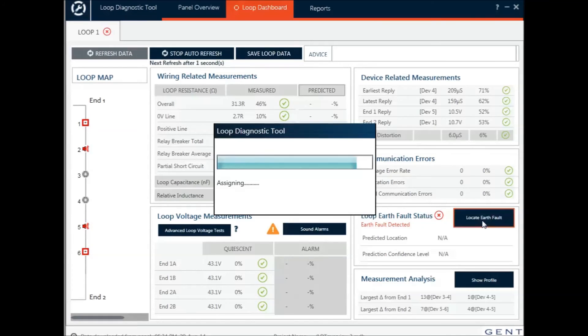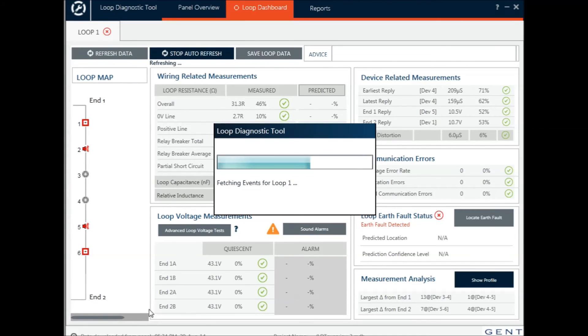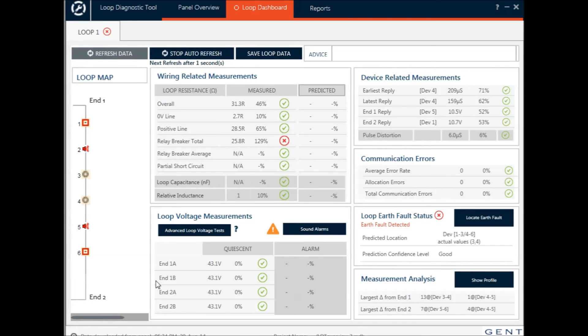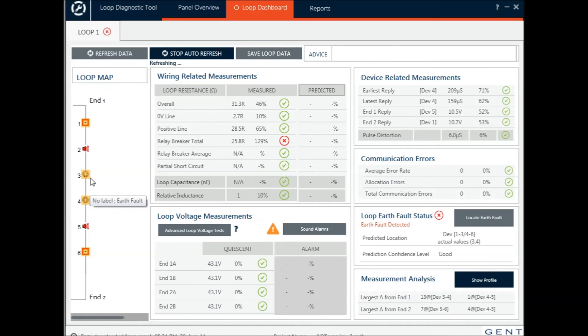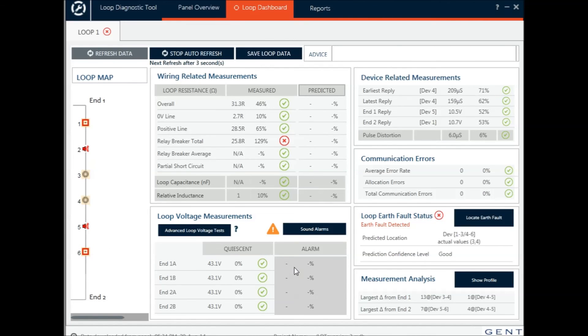To locate the earth fault, there's an active button here — click this, retrieve the information, and it's showing me that the problem is with the loop. I have potentially multiple earth faults on the devices that are flashing in yellow. Obviously this is a false situation — hopefully you won't have a loop this bad.